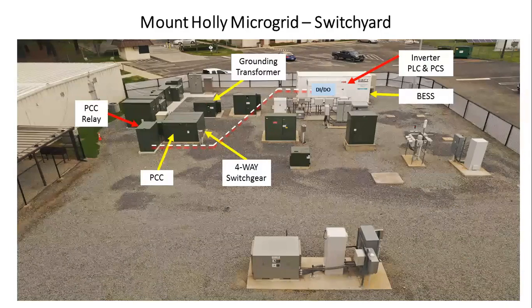Four-way switchgear essentially is used to, number one, we have way one, which is the point of common coupling. We have way two, which is connected to the transformer that transfers 12.47 kV over to the 480 volt system. We have way three that is tied to the grounding transformer, which is probably the most critical part of the microgrid.